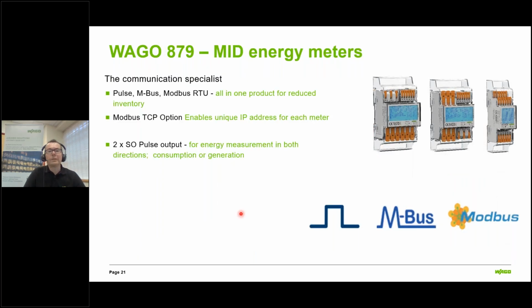So a little bit more on the WAGO 879 series. What we have is communications, which you'll remember when used as sub-metering in some implementations, we need to be able to record and manage the results that the meters are capturing. So the export of that data is achieved under a number of methods, either a simple pulse output, where you typically get a pulse for every kilowatt hour that the meter records. Or if you want much more information, we can either use what's called MBUS, which is short for meter bus, or Modbus. Now, in the case of our meters, we have Modbus RTU, which is a serial method of connection, which means the meters can be positioned around a site at quite long distances from the central energy management system.